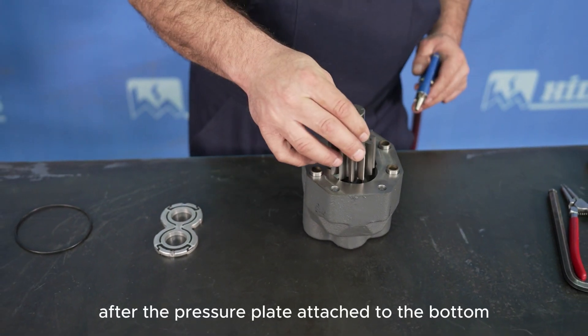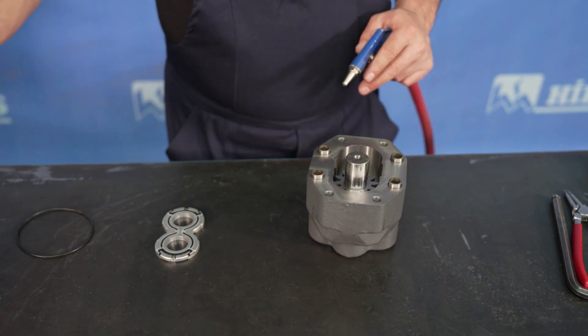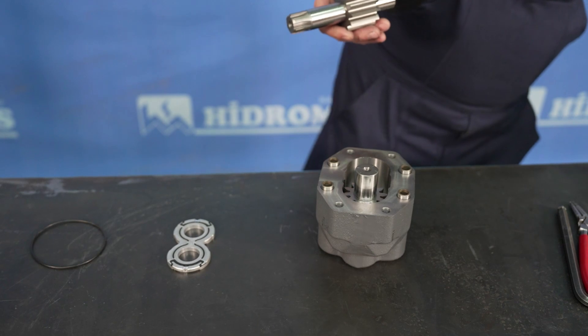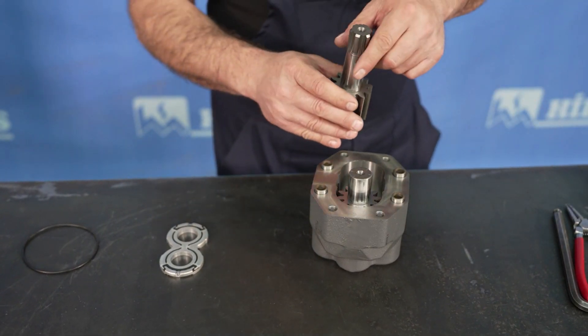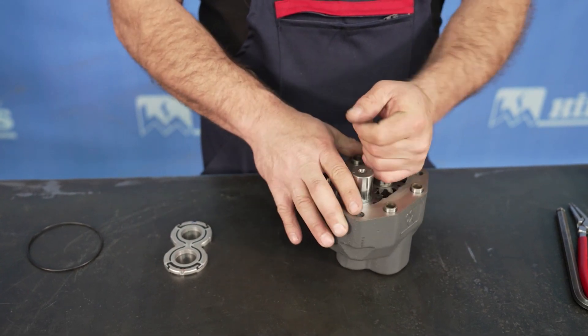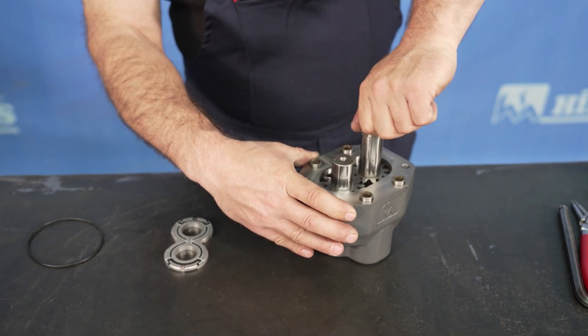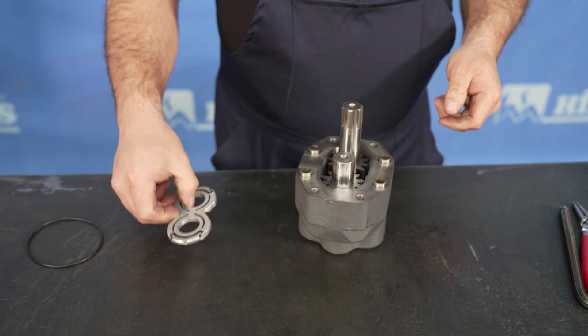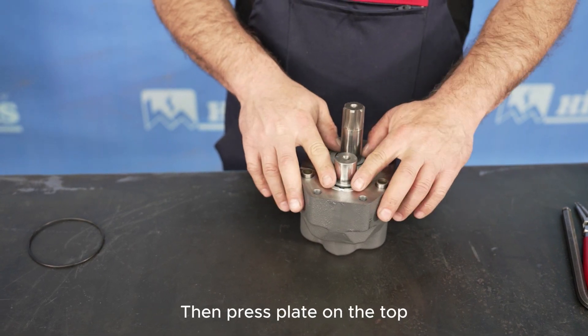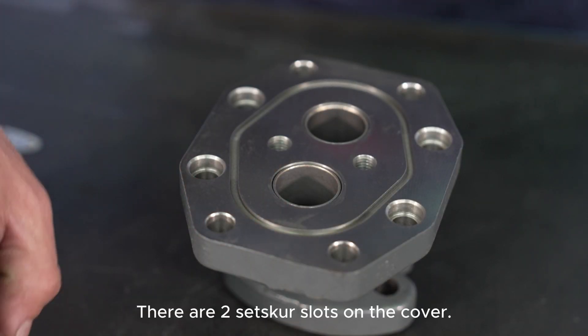After installing the pressure plate on the lower side, the short and long gears are assembled. In double rotation pumps, the placement of the gears in the housing is not critical. Then install the upper pressure plate with the O-ring and Teflon facing upwards.